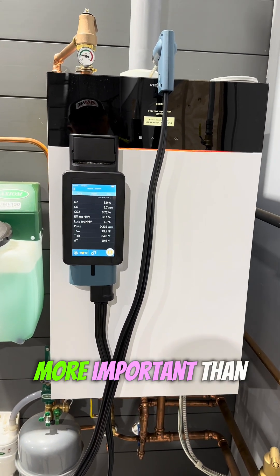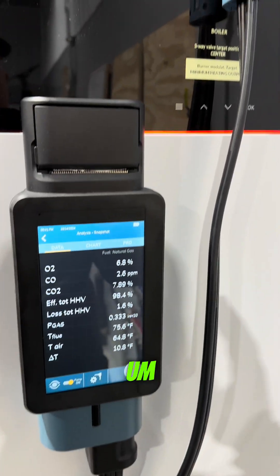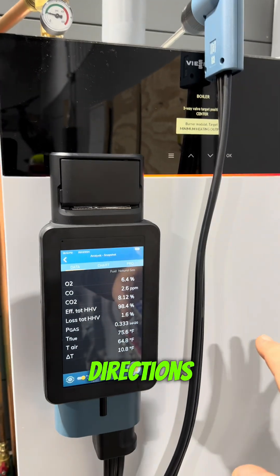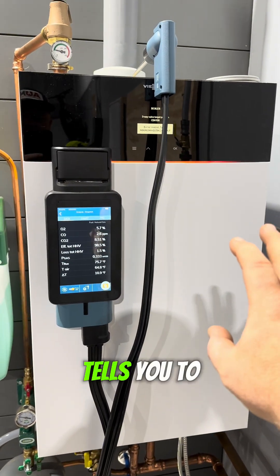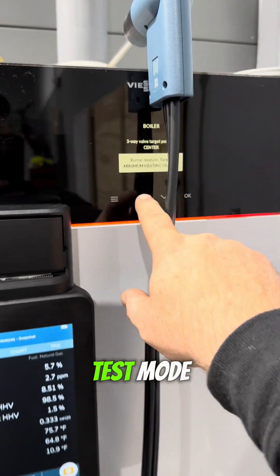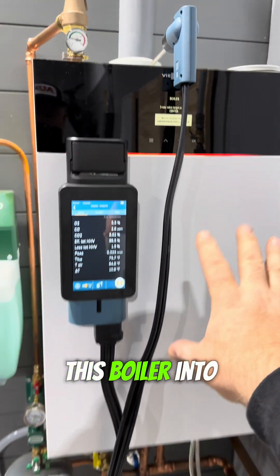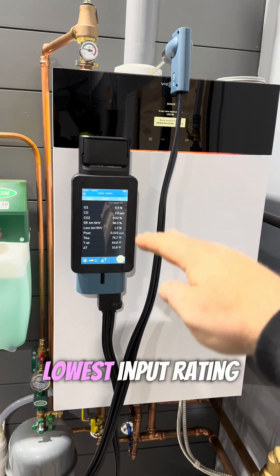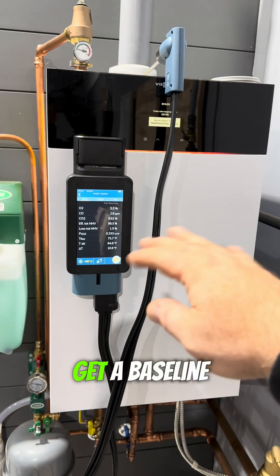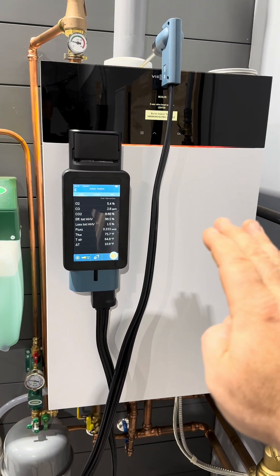Safety is way more important than efficiency. We can do that by following the directions in the manual. The manual for this Viessmann boiler tells you to use the actuator test mode built into the control — you're going to force this boiler into low fire. I need it to be at its lowest input rating so we can get a baseline and see how things are burning while it's on its lowest input.